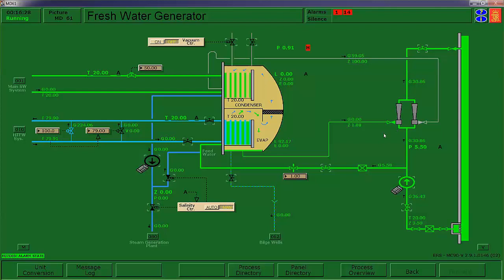Now this eductor, in this direction, is taking pressure from the feed pump through the eductor, sucking the brine out and overboard — so this is acting as a brine pump. On this side, the other eductor is taking a suction on the distillate condenser and drawing air out, and that's what's pulling your vacuum down.